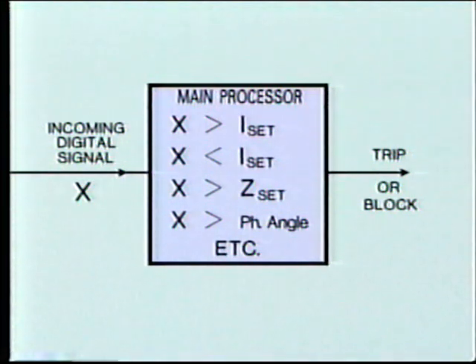The reference algorithm will, of course, be in digital format to represent one or more mathematical formulae, which in turn simulates all of the operating parameters and constraints of the protected circuit. The algorithm may be set up to represent, say, an overcurrent relay, directional relay, negative sequence relay, differential relay, or any other protection relay.